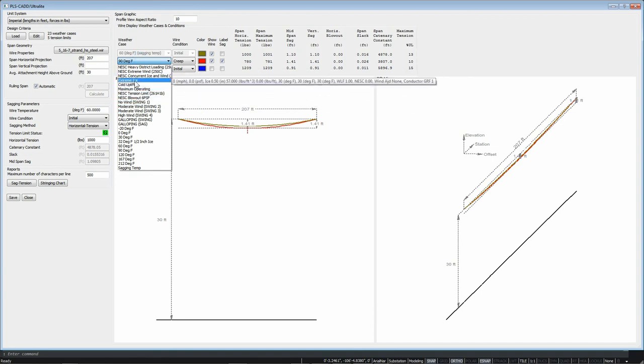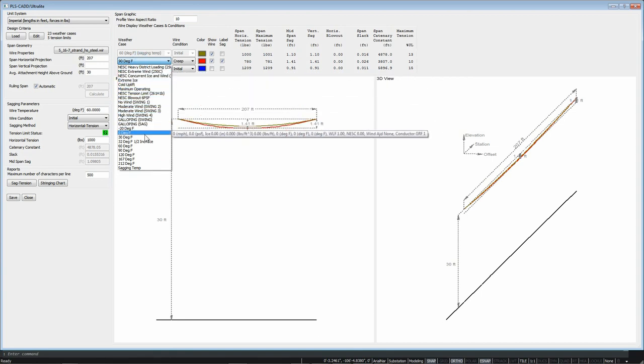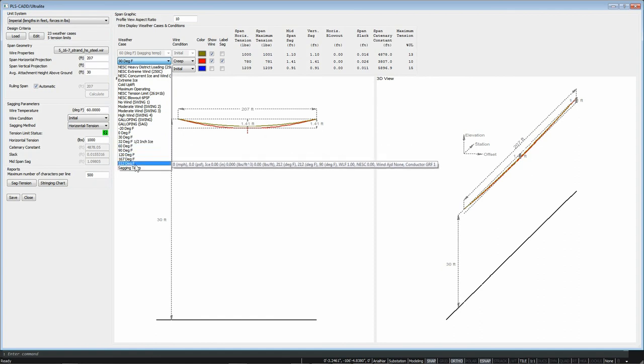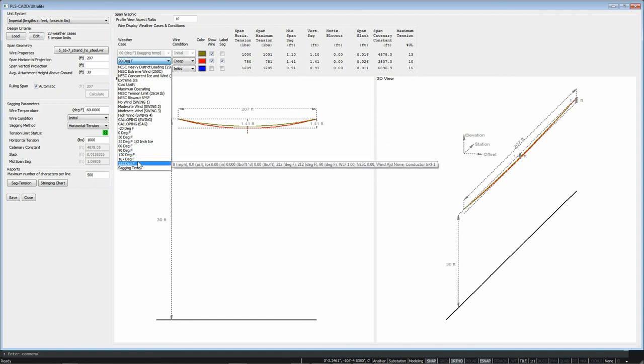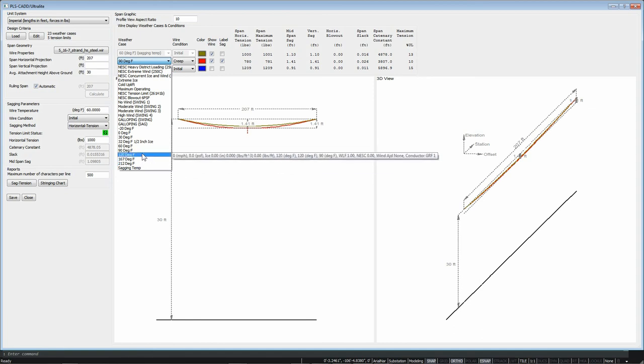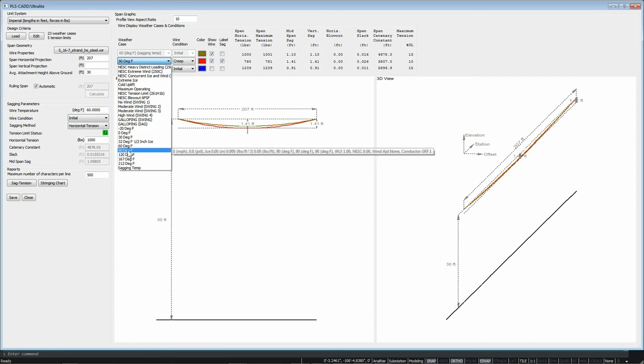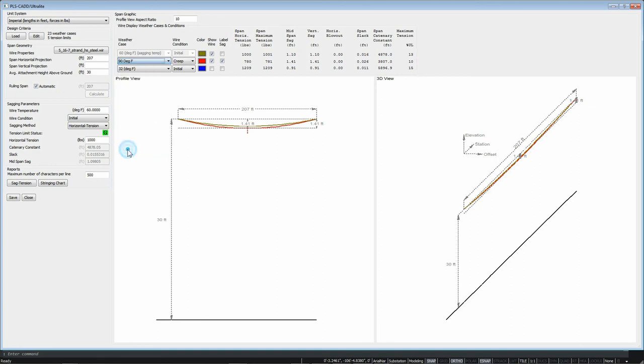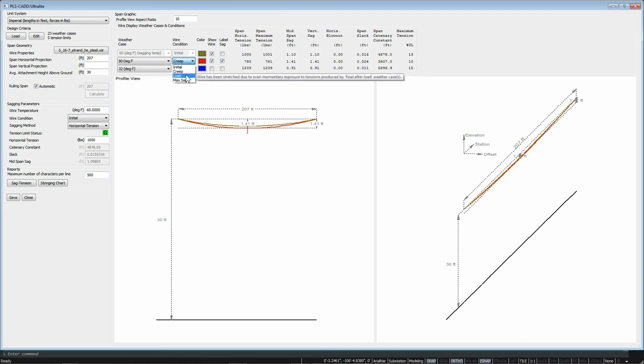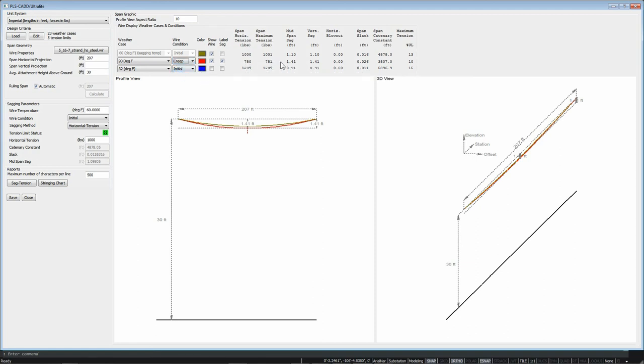What I'm using here is a 5/16ths seven strand high strength steel cable for overhead ground wire. Now we need to determine what conditions we want to use to sag this in. The program gives you a number of different conditions. We obviously don't want to use 120% of the 212 that we normally use for transmission or distribution lines because we're not going to be putting any amperage load on this, so we're looking at strictly a temperature loading. We will assume that even on a very hot day if you've got lightning and rain, 90 degrees would be an upper limit. Based on 90 degree F and adding in for creep so that we get a final sag, we want to ignore load and this is final sag with creep. We see the catenary constant for this condition is 3807.